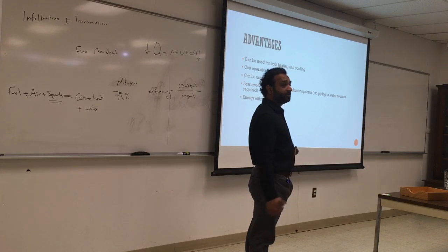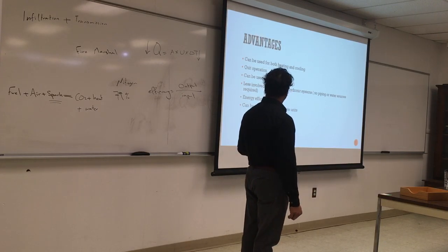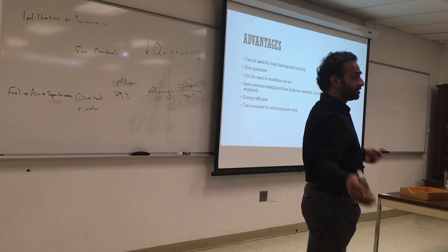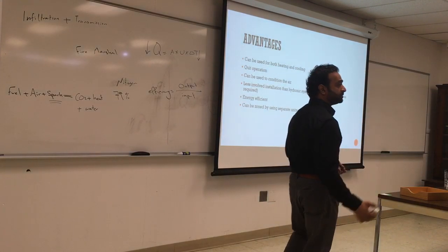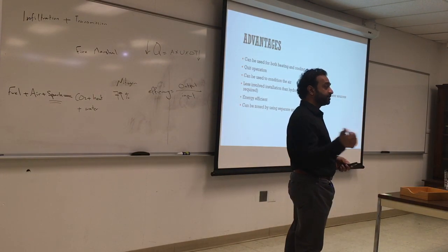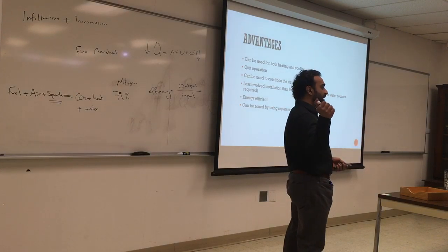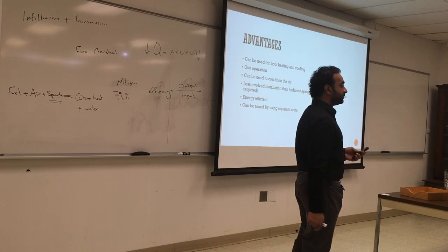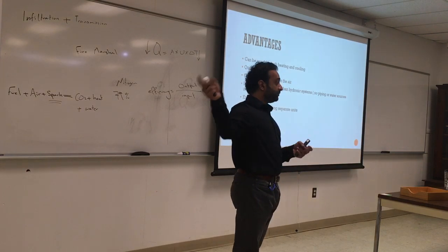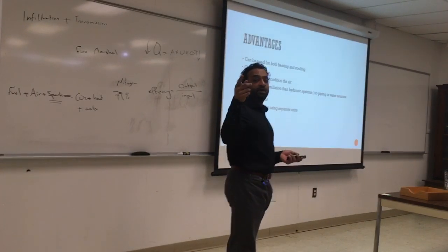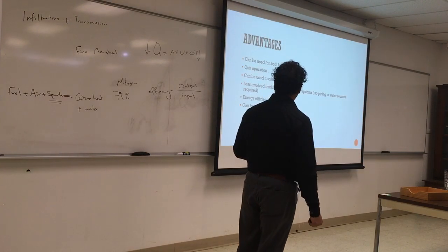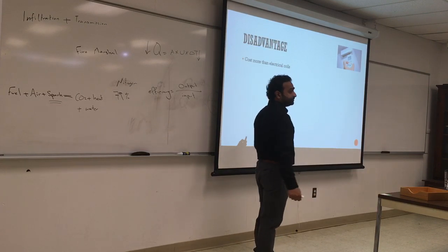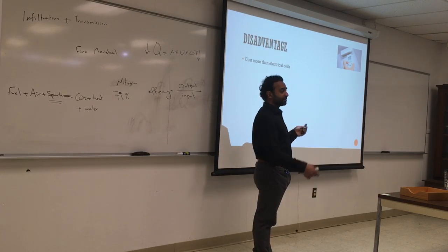Energy efficient, this is very energy efficient compared to a heating coil. It can be zoned by using separate units. So for each floor you can have one of those, so each area you can have one of those. And one cooling or heating unit can have from four to six inside units. So you have only one AC outside, but it can go to each one of those zones. So now we have one unit over there, it has four outlets. We have four inside units for one condenser. Its disadvantage, it costs more than electrical coils. The cost, of course, is higher than putting just coils inside every room.